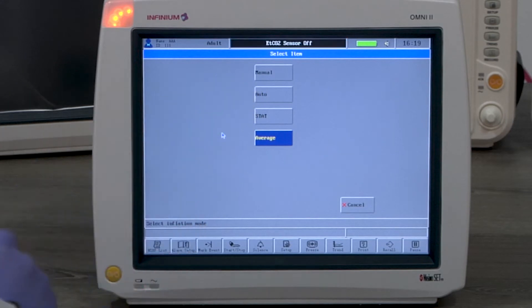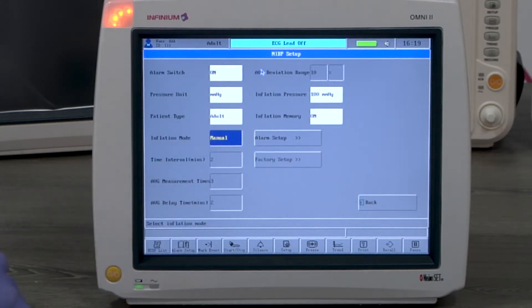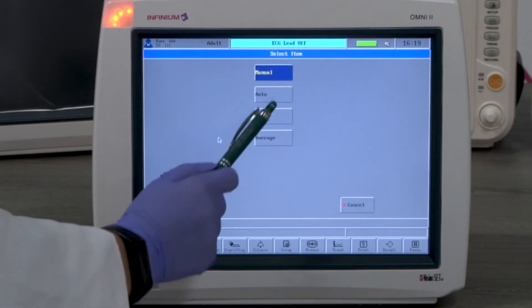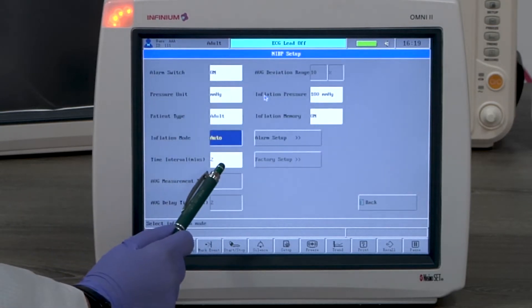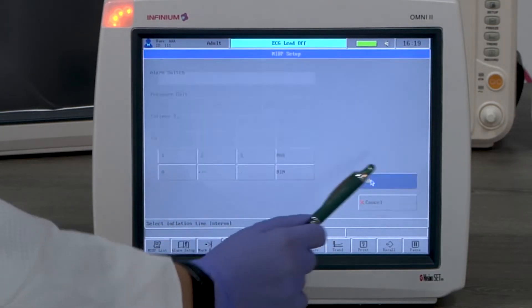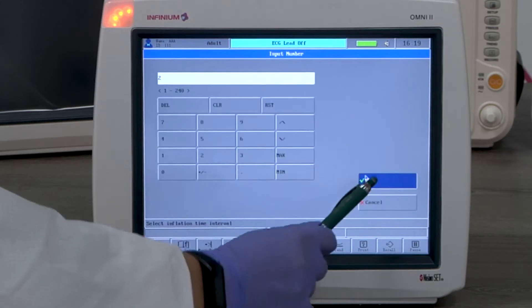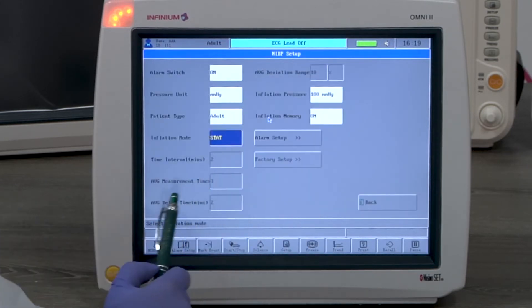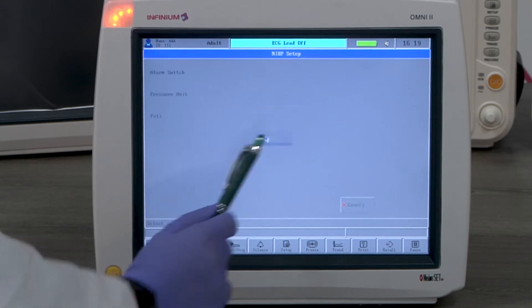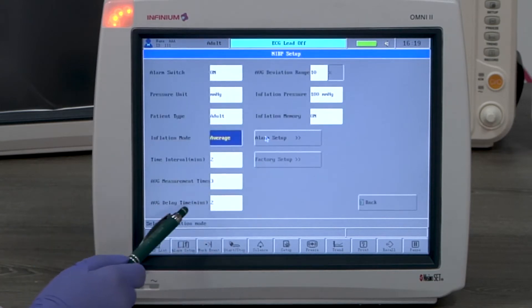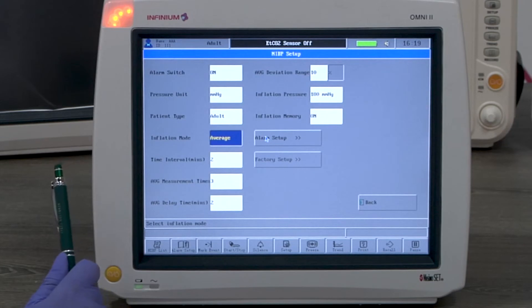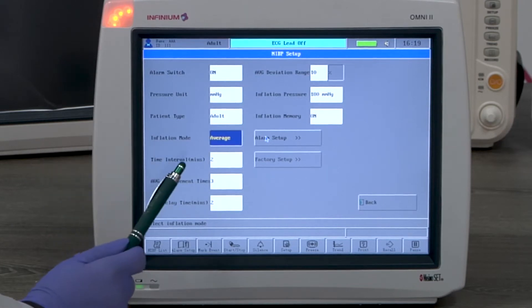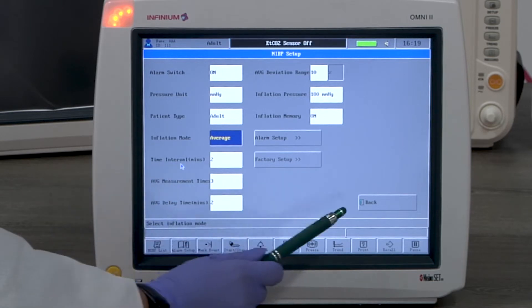We have four inflation modes to select. Manual mode only measures when you give a command. Auto mode measures automatically according to the set interval. Stat mode takes three measurements when you give a command. Average mode takes multiple measurements with the delay time set between each measurement and displays the average results from these measurements. Another set of measurements start according to the set interval.